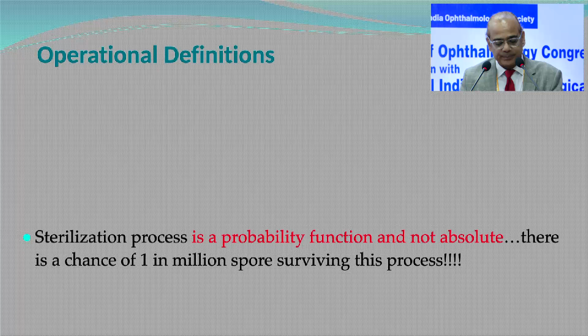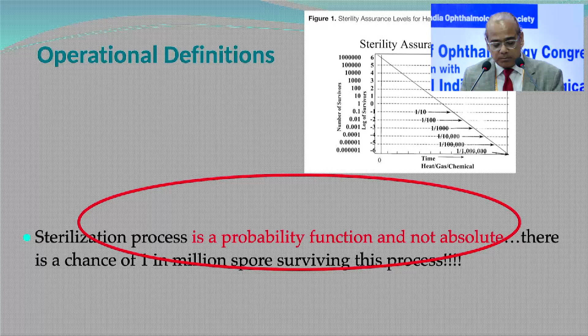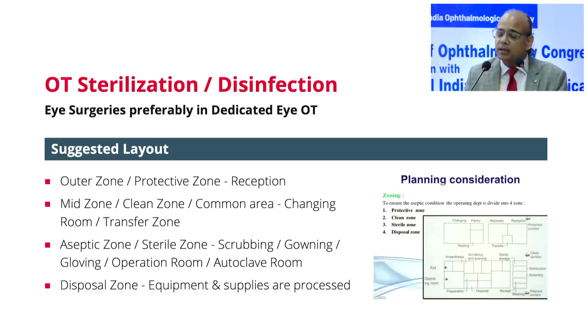So the sterilization process is a probability function and not absolute. We must understand this, and there is a chance of 1 in a million spores surviving the whole process. Regarding OT sterilization or disinfection, eye surgeries need to be done in a dedicated eye OT. This is the suggested layout in short. There needs to be an outer zone or protective zone at the reception. The mid zone, clean zone or common area is the changing room or transfer zone. Then the aseptic or sterile zone for scrubbing, gowning and gloving, the operation room and the autoclave room. And then of course the disposal zone, where equipment and supplies are processed.